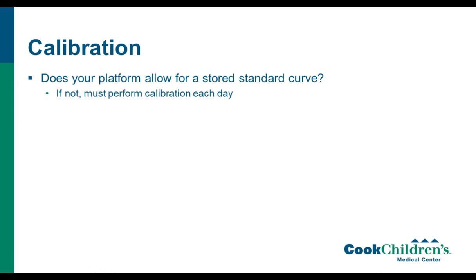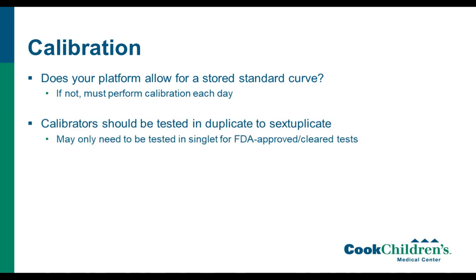So now that you have materials picked out, you want to know, does your platform allow for a stored standard curve? Can you put together a calibration curve and then store it and continually use it each day? Some instrument platforms require you to perform a calibration each day, and then you'll need to create a new standard curve each day of testing. When you're creating your standard curve, you'll want to run your calibrators anywhere from duplicate to sextuplicate, which is 6 replicates. Some FDA-approved tests require these only to be run in singlet, but a lot of times, if we're creating a new calibration curve, we'll run ours in sextuplicate, just to make sure we have a lot of replicates to make sure we have an accurate curve and detect the variability that may be there.